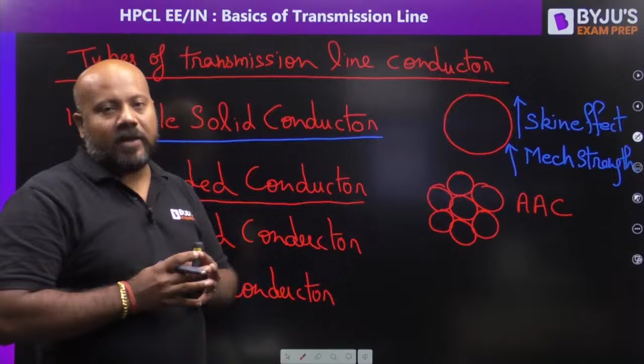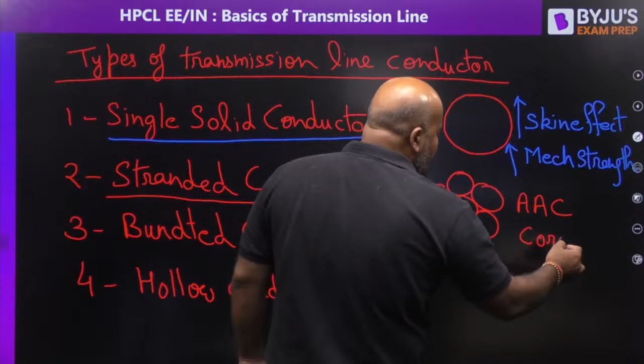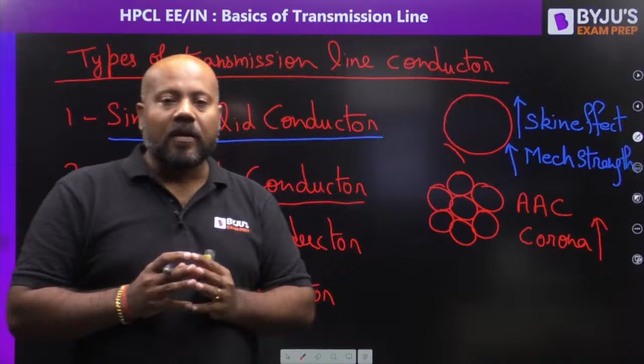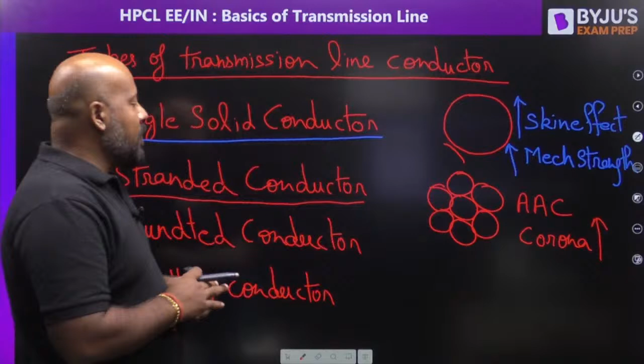But this stranded conductor is also going to have a big disadvantage. What is that? This conductor is going to have a significant amount of corona. Corona is going to be very high. Why is corona high? The surface of this stranded conductor is not smooth. It is going to have sharp corners. And you know that at the sharp corners, the electric field stress is going to be very high. And when the electric field stress is very high, corona is going to be very significant.